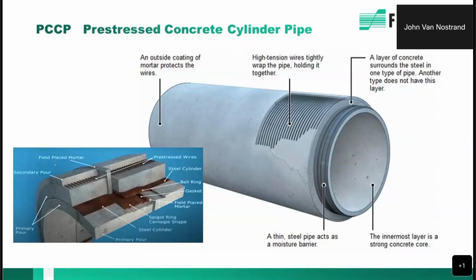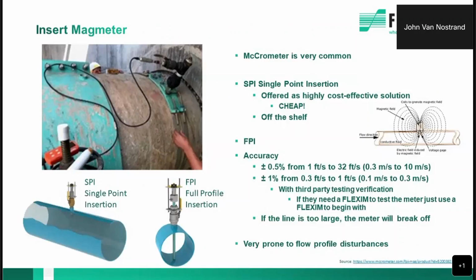We've actually done our homework on what the sound speed measurement should be through this pipe, and we programmed that in, and we actually have a file for that. This is a very common installation for water systems with concrete pipe. You'll wind up having to tap the pipe and insert a Magmeter. It's a point velocity measurement. What I mean by that is a single point where they're measuring in the velocity stream. They also have averaging style Magmeters where they might average a number of points with multiple sensors in order to improve their accuracy. But the point is, these meters are problematic. They really degrade the integrity of the pipe when you start drilling into the concrete pipe and so on. So you no longer have to do that.